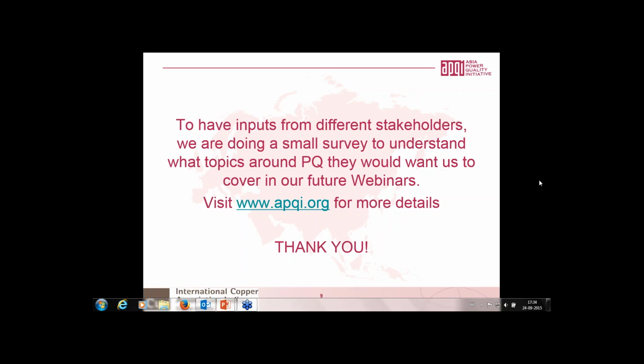So for other utilities, we have to take that up, right? Yeah, correct. Because at the end of the day, if you have a power quality meter, it's a secondary issue whether it is owned by the utility or by the customer. But if the customer wants to know which facility in his premises is creating a power quality issue, then within his plant he will be required to install power quality meters in his distribution system inside.